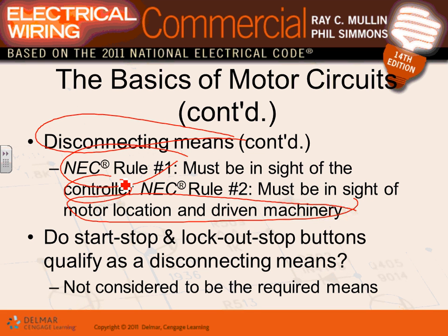Start and stop push buttons like these. These start and stop push buttons, guys, do not qualify as a disconnect. Start and stop push buttons do not qualify as a disconnect.